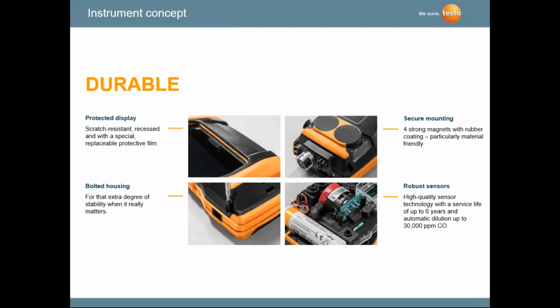It has large magnets on the back, so you can put it on the boiler or the furnace itself. You can unscrew the case itself with four screws, and you can get internally into the instrument to see the 2 or 3 sensors that you may have in that analyzer, and those sensors are replaceable in the field after a period of time. The sensors last up to 6 years now. I'm talking primarily the carbon monoxide sensor and the O2 sensor, the oxygen sensor.